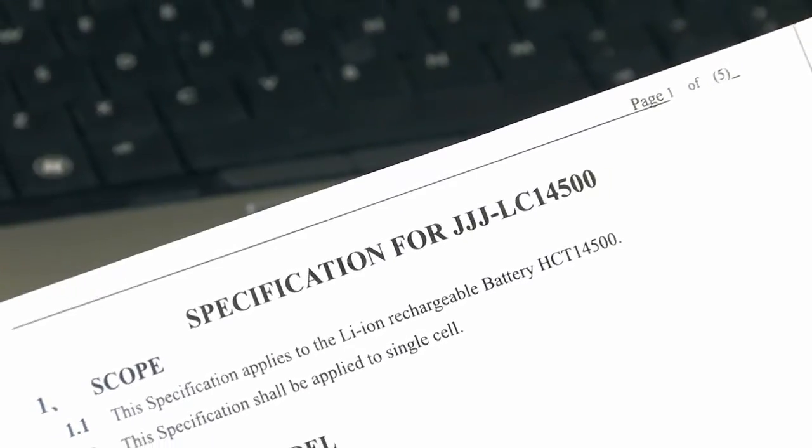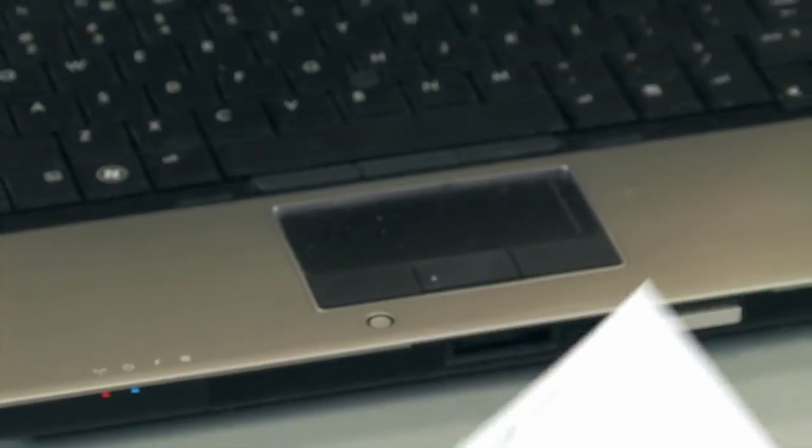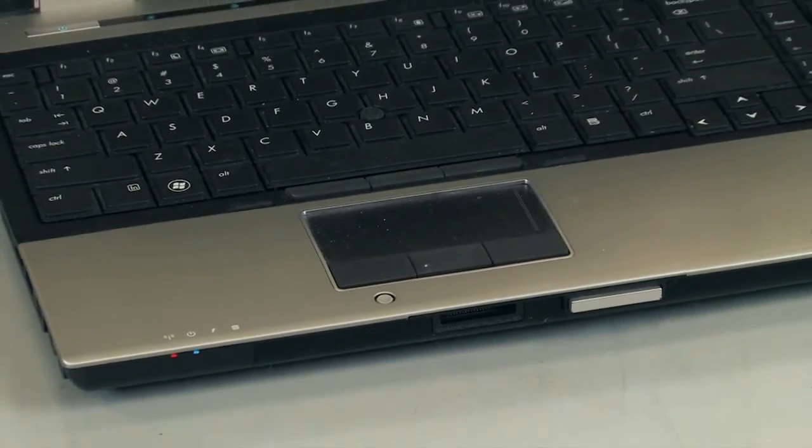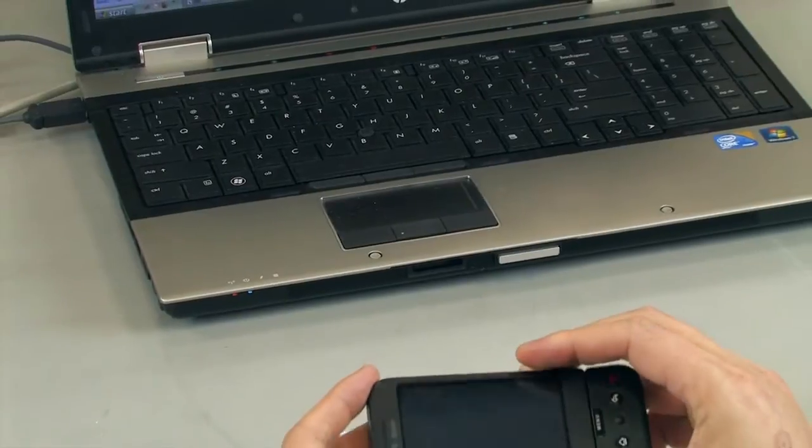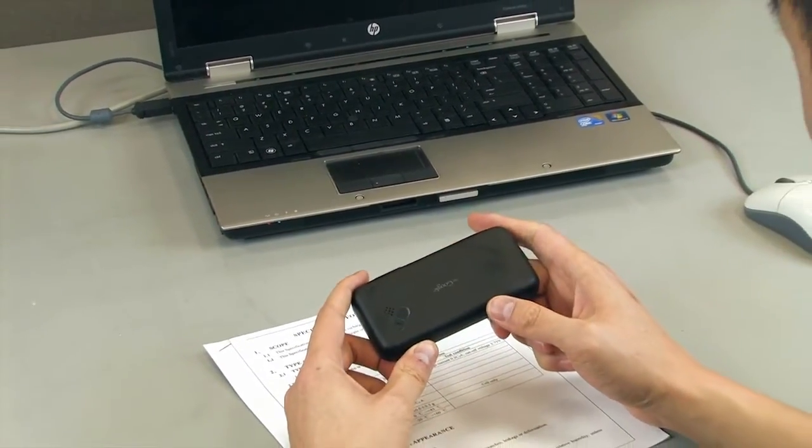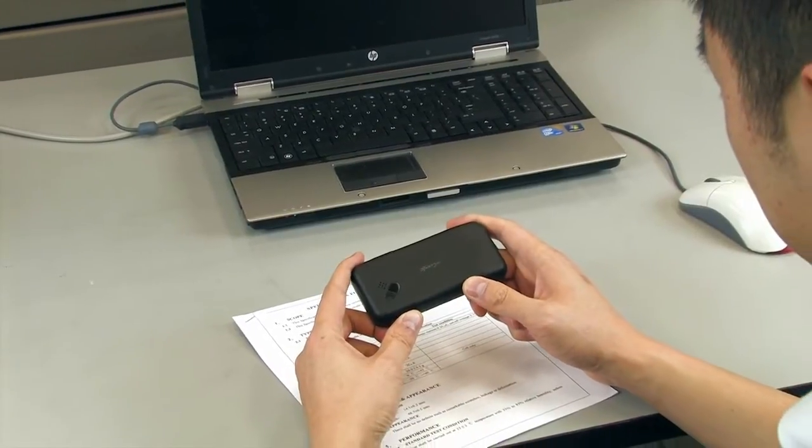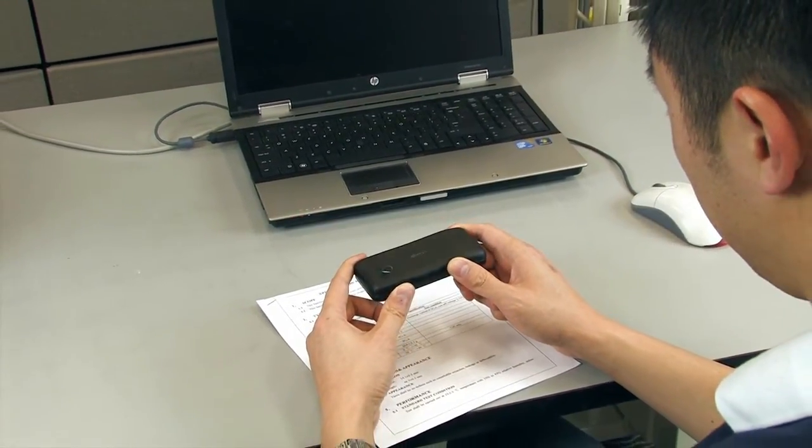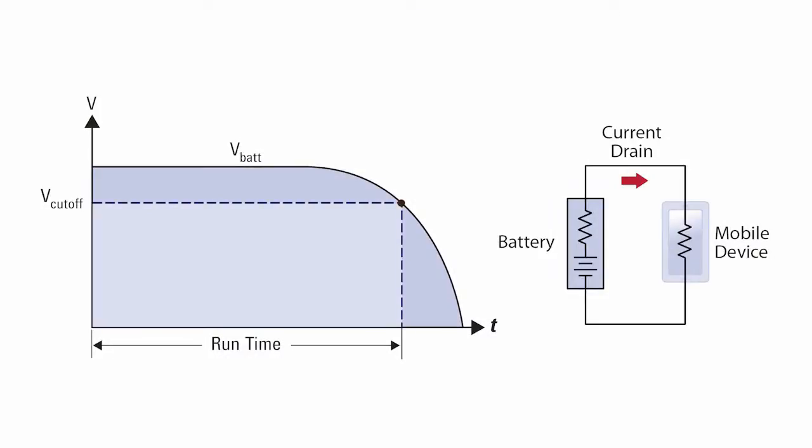If you determine a device's runtime based solely on a manufacturer's datasheet without validating the battery's ratings, your results are likely to be inaccurate. The stated capacity is often based on ideal conditions and represents the maximum charge you might obtain from the battery. Actual capacity will usually end up being less when you verify it in your application.